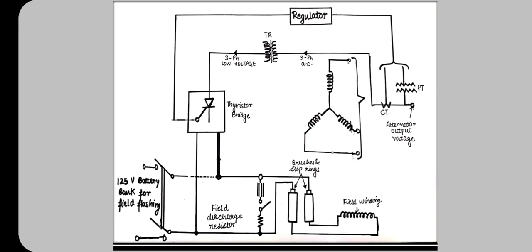The second one is, since there is no separate rotating type exciter, the system is free from friction, windage and commutator losses that occur in the exciter. This makes the system more efficient and reduces the maintenance. So this is all about the static excitation system.